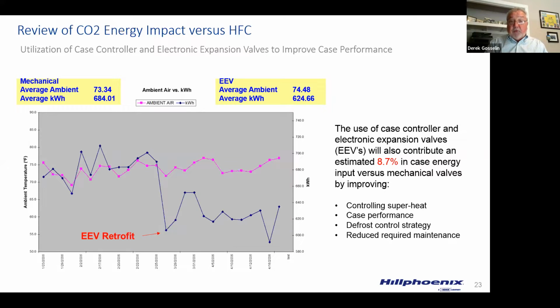One advantage with CO2 is you have to add case controllers and electronic expansion valves. Yes, that increases your case cost, but there's also an energy savings — EEVs can give you an 8% savings, helping control superheat with an electronic expansion valve versus a mechanical valve, giving better case performance. That's something we can quantify, but it also leads to better case temperatures, better product temperatures, maybe even a food safety advantage.